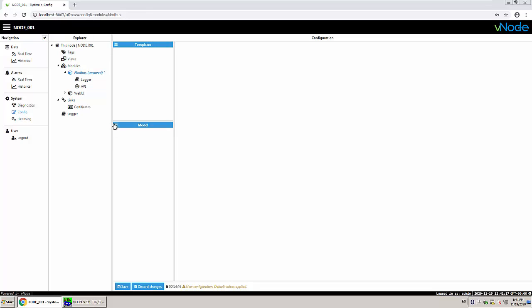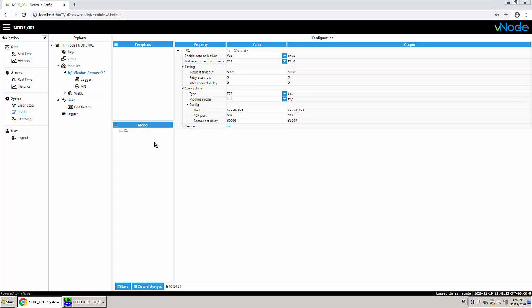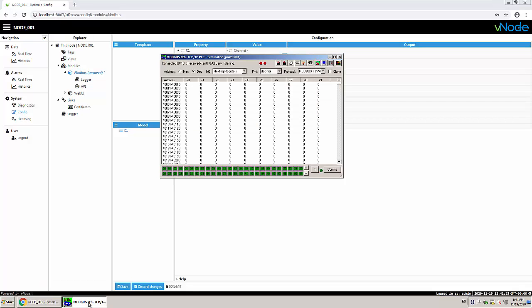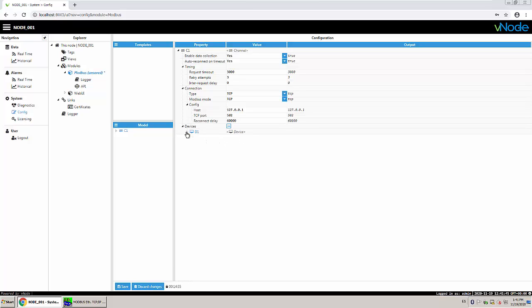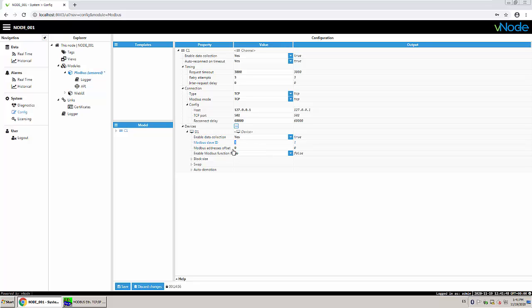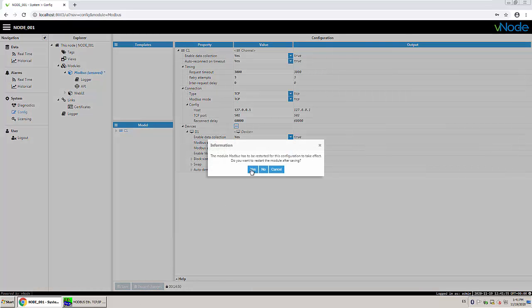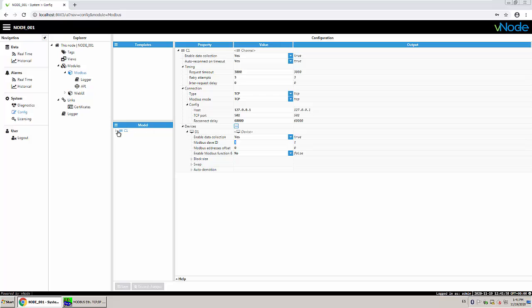Inside my Modbus client I'm going to create a channel. You can create as many channels as you want, connecting to as many devices as you want. I'm going to create channel one, connecting to my simulator which is on localhost. The port is correct. At this IP I have a device called device one, and I'm calling it d1. I'm starting the module — I now have channel one and device one.